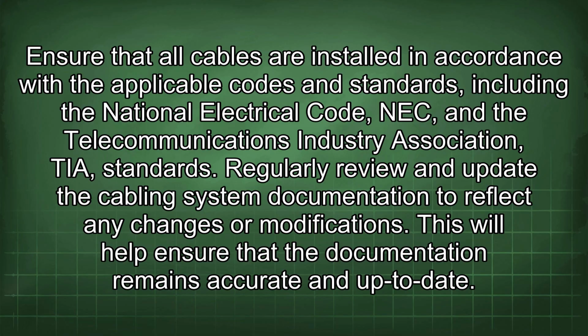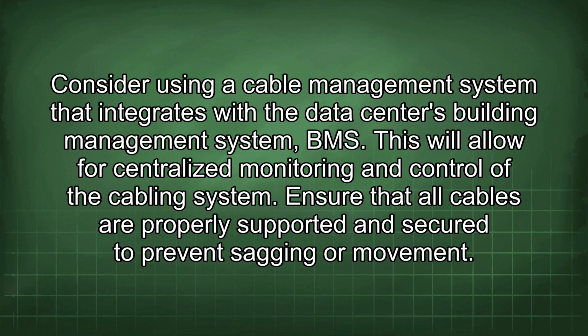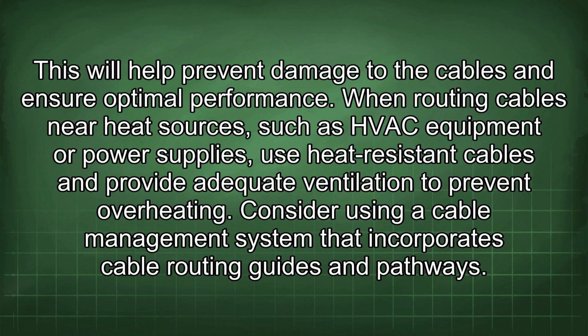Regularly review and update the cabling system documentation to reflect any changes or modifications. This will help ensure that the documentation remains accurate and up to date. Consider using a cable management system that integrates with the data center's building management system (BMS). This will allow for centralized monitoring and control of the cabling system. Ensure that all cables are properly supported and secured to prevent sagging or movement. This will help prevent damage to the cables and ensure optimal performance.